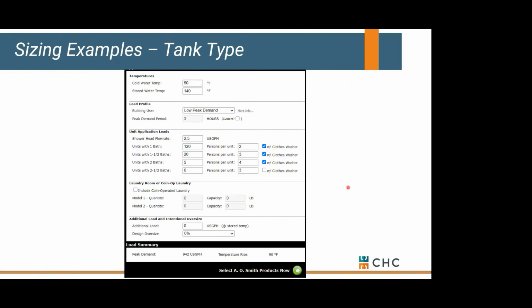So one of the first things we might want to do is maybe look at some tank type water heaters. Okay, what are our options here? Well, we might go to A.O. Smith, hotwatersizing.com, enter our conditions, 50 to 140, and then we've got a certain number of 1 bath, 1.5, and 2 bath units. We might assume each one has a clothes washer inside of them. And if that's the case, we're going to end up with a peak demand here of 942 gallons per hour. So I need to find a water heater that will recover that. Where are we going to go from there?